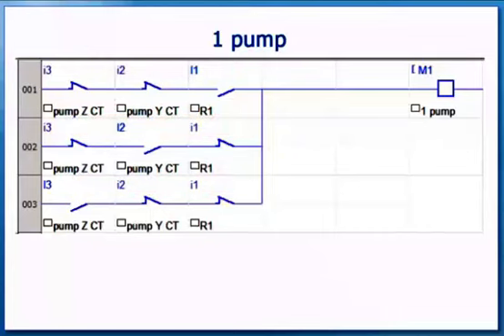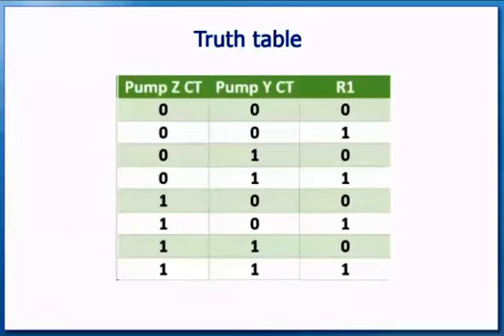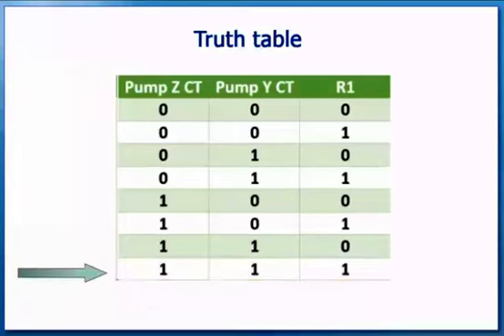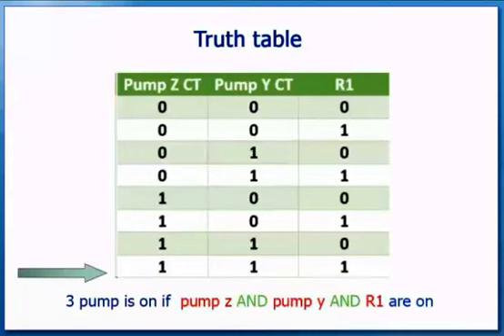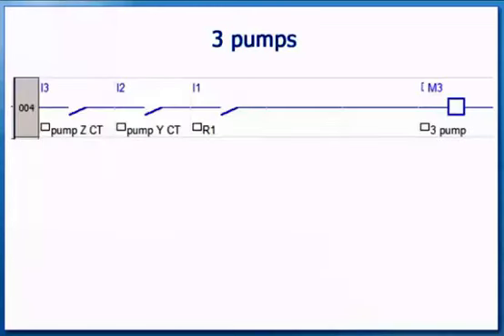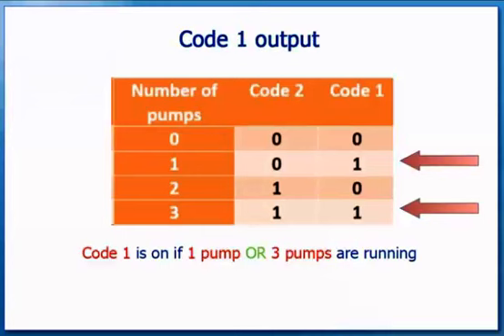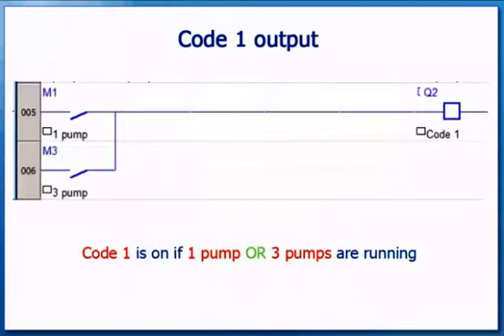The next step is to create the three pump internal relay — an internal relay that indicates when all three pumps are running. Identify which line of the truth table is true for all three pumps running: there is only one, the bottom line. So the three pump relay is on if pump Z is on AND pump Y is on AND R1 is on. The program for three pumps consists of a single AND function of pump Z CT, pump Y CT, and R1. Code 1 comes on if there is one pump or three pumps running — we combine the one pump and three pump relays with OR to operate the Code 1 output.